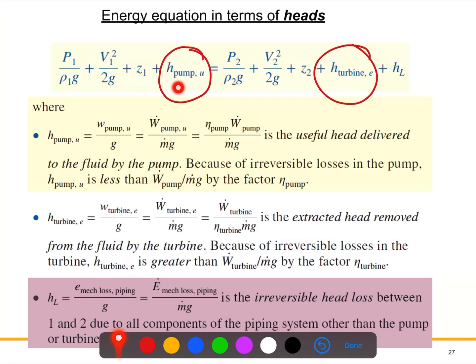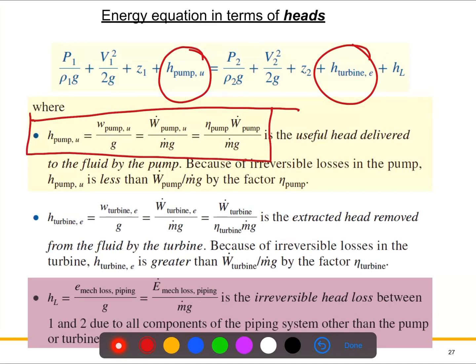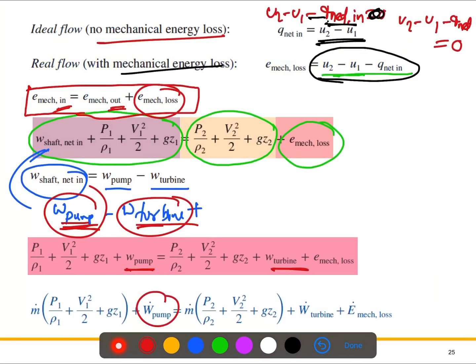When we introduce heads, the energy equation becomes expressed in terms of pump head H_pump and turbine head H_turbine. The pump head is the maximum height to which a pump can discharge water — essentially the energy per unit weight delivered by the pump. To obtain the pump head, we divide the pump power by ṁg. The same approach applies to the turbine head. The energy equation in terms of heads is the most commonly used form in engineering.